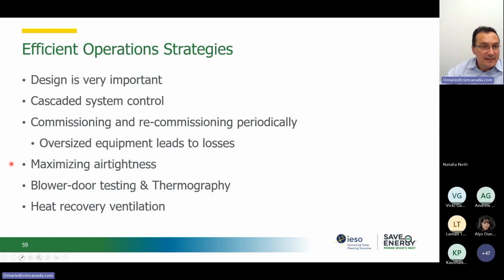Increasing the air tightness, so basically reducing the infiltration rate. We can continue to do the caulking and the weather stripping on a regular basis as part of operations. Once in a while, I wouldn't say it's a norm yet, but I've seen more buildings, we can use technology to help us identify problems. Thermography is applicable to any building. Blower door test is easier to apply for smaller buildings, more complex for larger buildings.